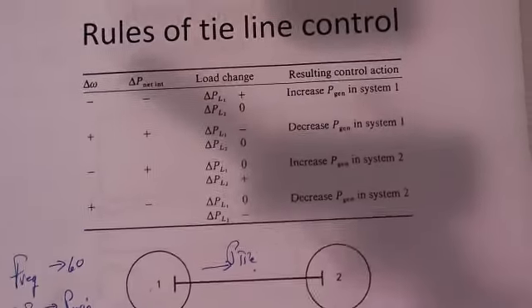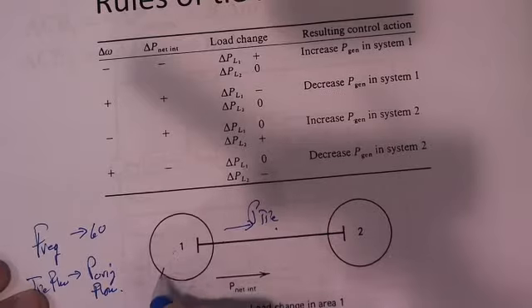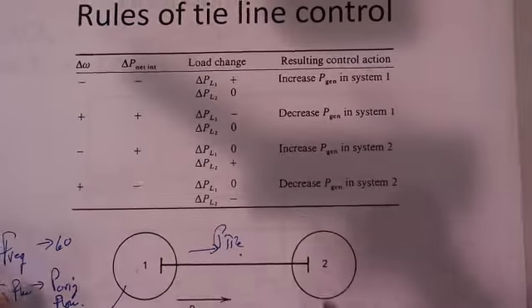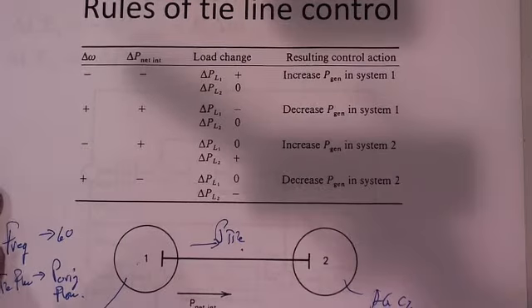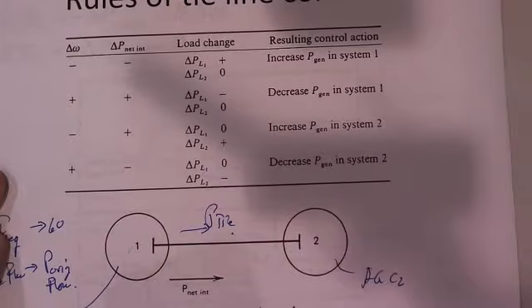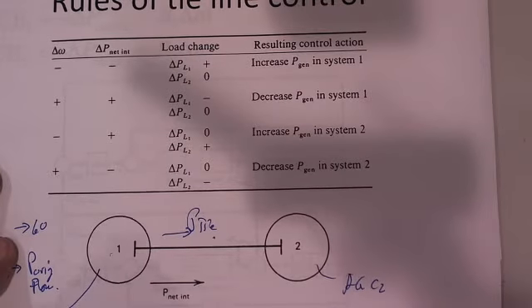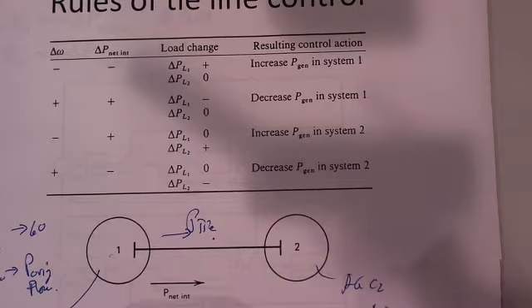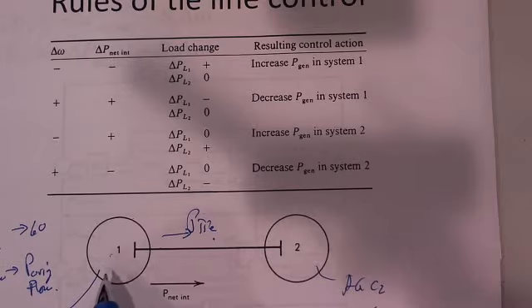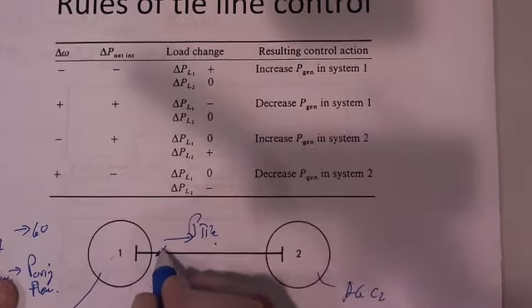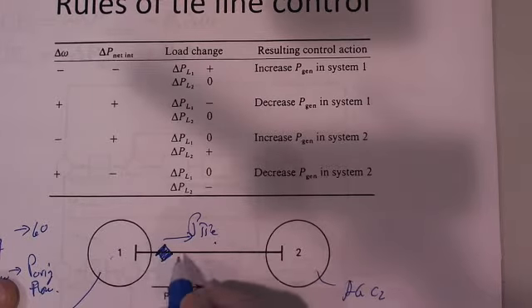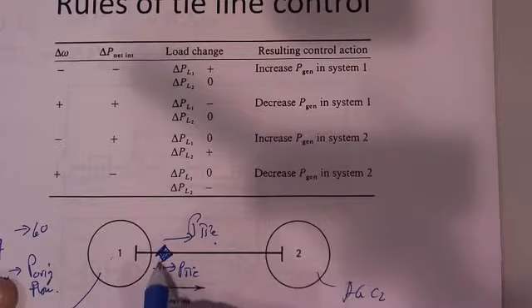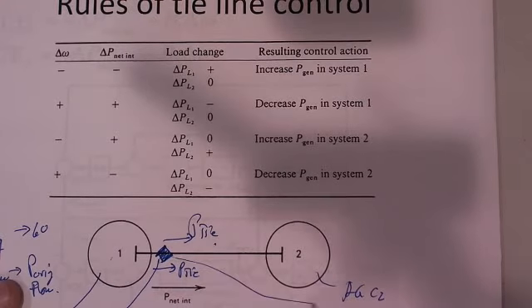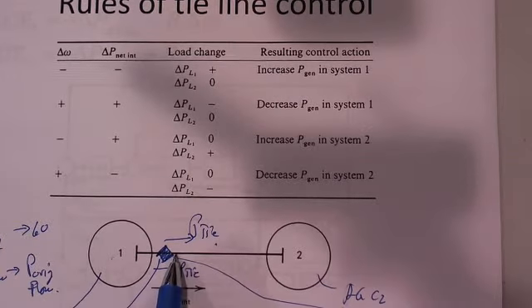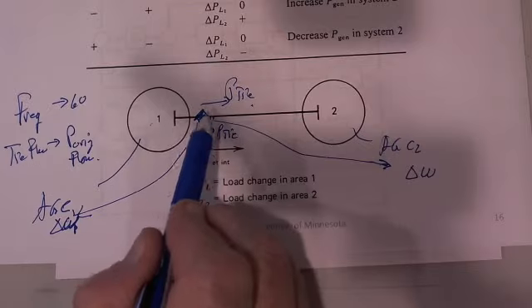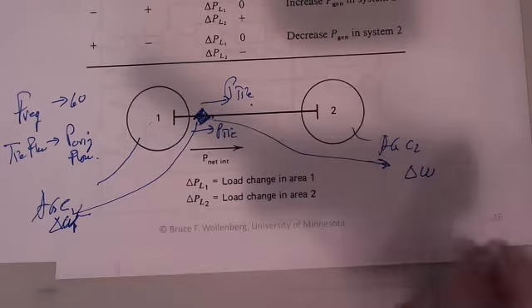And to do that, we have two inputs. There's an AGC here, AGC1, and here's AGC2. He is measuring delta omega at, let's say, a common bus, but we know it's the same frequency everywhere. And then there's a measurement. Remember our state estimator? I'll put a measurement, a diamond like this, and that's measuring P tie. We take that measurement and give it to both, so they both know how much the flow is deviating on the tie, and we know what the frequency deviation is across the system.